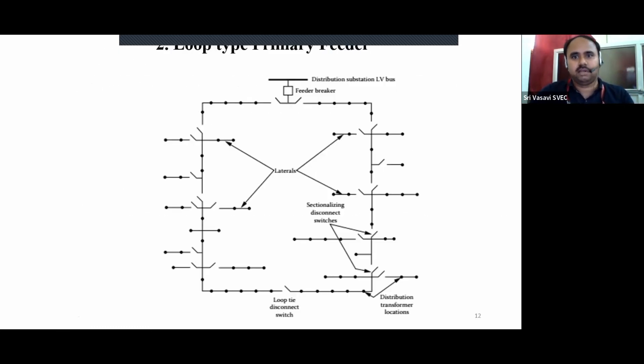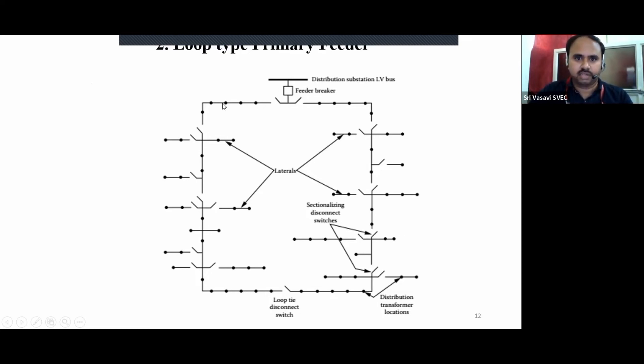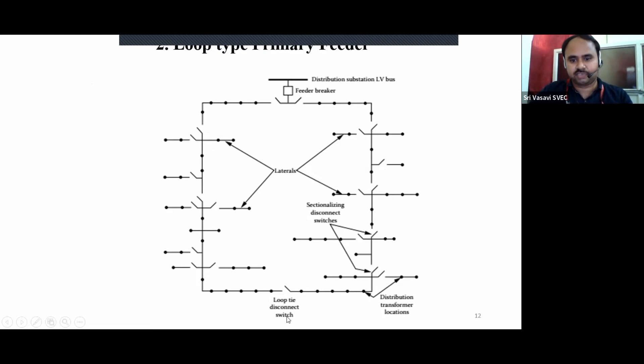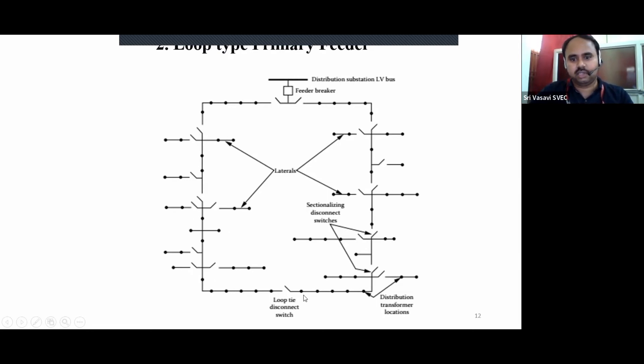The next type is the loop type or ring main primary feeder. It includes a distribution substation LV bus, feeder breaker, load points with laterals and sub-laterals, sectionalizing disconnect switches, and a loop tie disconnect switch. If a fault occurs in any one section, the loop tie disconnect switch is opened to avoid interruptions for the remaining consumers. This is the advantage of using the loop tie disconnect switch in the loop type primary feeder.